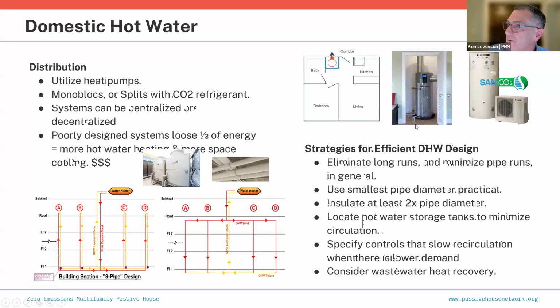Now, one thing folks may do is utilize the hot water heater with a heat pump, which is entirely possible. There's an issue with noise where the compressor and condenser are right there, and we want to duct the cold air that it throws off when heating the water to another space. We don't want to heat the apartment space unintentionally by making hot water, which throws cold air into the apartment. One way is to possibly have access from the corridor and do it that way.